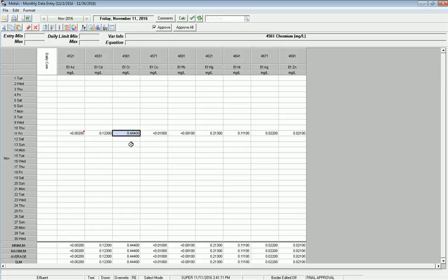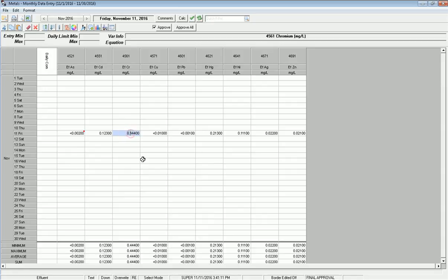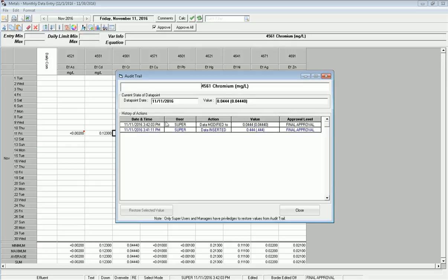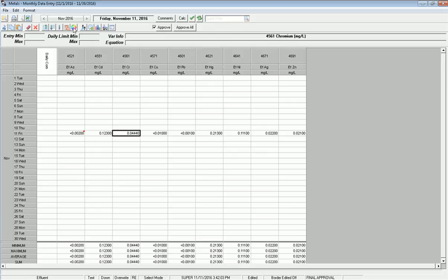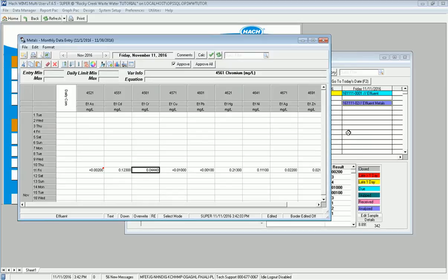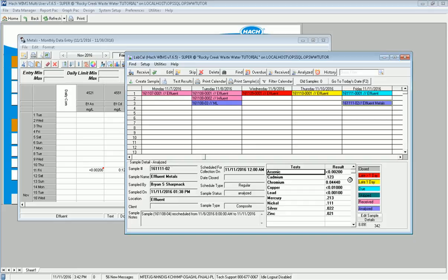Conversely, if I want to go in here and say, you know what, that 0.4400 there, that's not right, it was 0.044, I can edit that number. That goes into my audit trail. Bring up right here, so you see that it was entered, and then it was edited. Now, if I go back into LabCal and pull that up, notice the result is now changed to 044. So they're writing to the same place, the same variable. LabCal gives you another way to enter that data. As a matter of fact, you can enter that data completely through custom data entry or monthly data entry, and it would show up here. You can also use it like I just did.